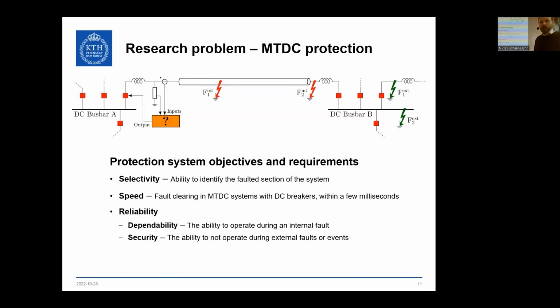In DC, if you get a fault, the transients are very quick. The drawback of AC in terms of cables is that you get reactive components, but in fault cases that actually helps you. In DC, everything contributes immediately, so even a fault in one part of the system will be seen very quickly by all parts. Whereas in AC, a fault in France does not necessarily cause a big disturbance in Germany.